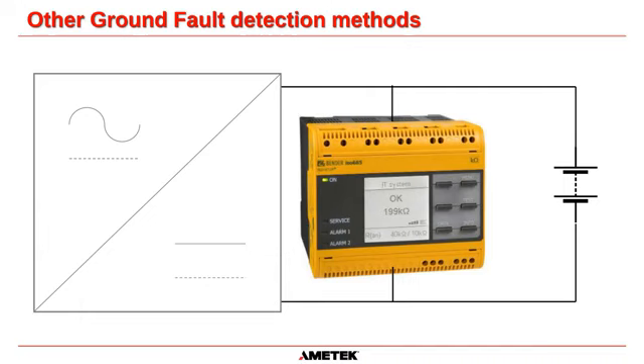And this Bender does not create that potential division between positive and ground and negative and ground. If you have a Bender system on a DC system, it will not have the 67.5 volts to ground from positive or 67.5 volts to ground from negative. It does something completely different, so bear that in mind. I don't have time, nor the knowledge, on what these Bender systems do. I used to, but it's been a long time since I've used them. So if you do have a Bender system on your DC system, you're not going to measure the halfway point between positive and ground and negative and ground.